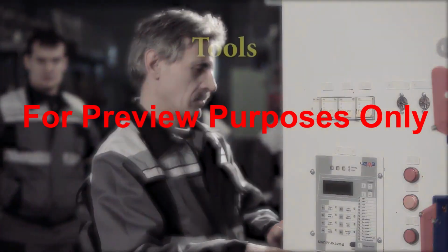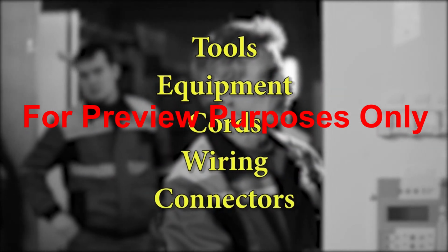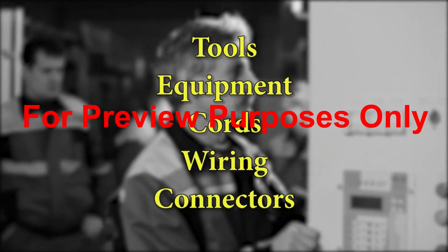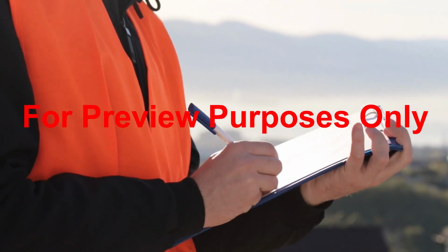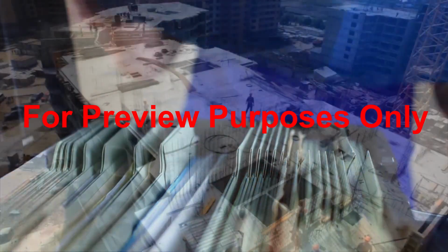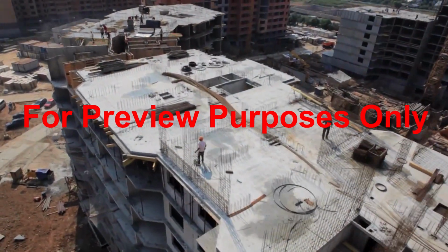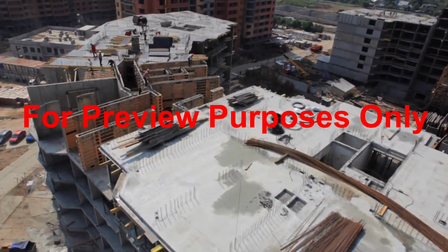The program designates qualified personnel who test tools, equipment, cords, wiring, and connectors for grounding continuity on an ongoing basis. A copy of the written program must be made available on each job site, and results of the testing must also be kept on file. However, on some job sites, it may not always be possible to ensure that a continuous ground connection is available in all areas or for all equipment.